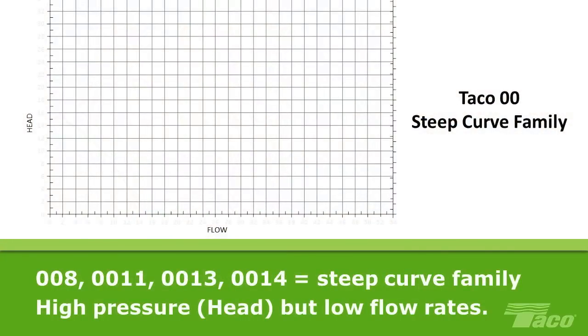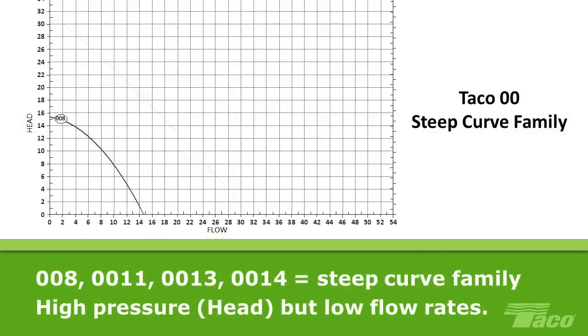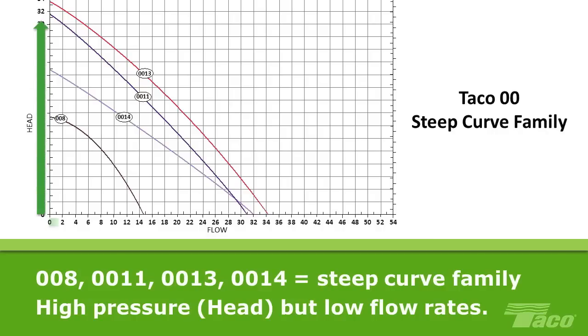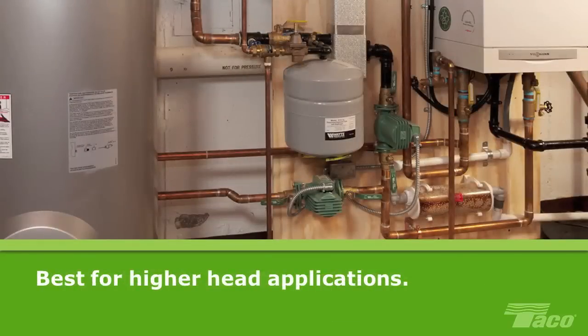On the other hand, models 008, 0011, 0013, and 0014 are all in the steep curve family. Compared to pumps with a flat curve, these circulators can generate a lot of head pressure but comparatively low flow. These circulators are best for higher head applications, such as high head loss fan coils, air handlers, and heat exchangers.